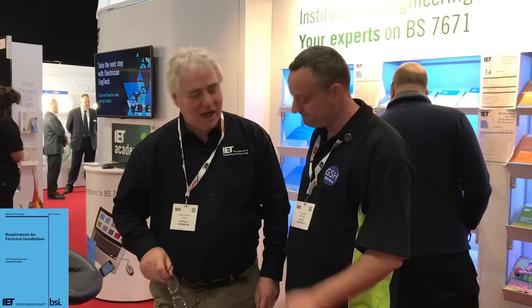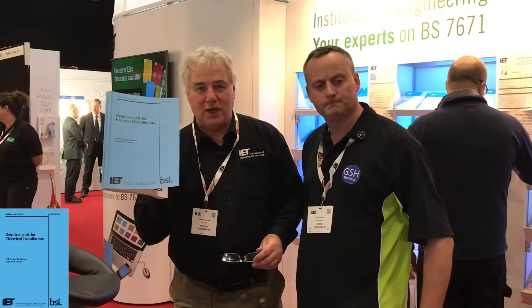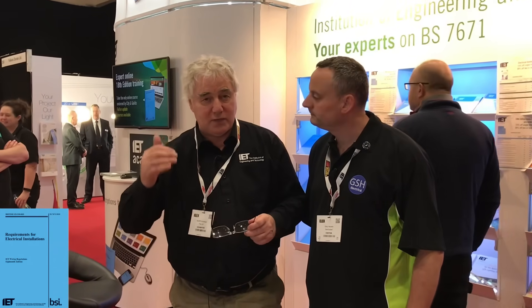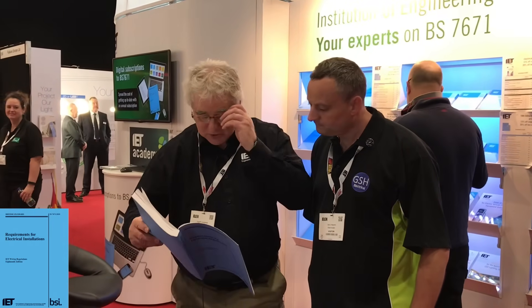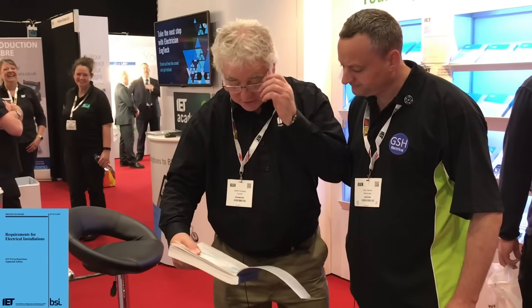I'm with Jeff, Chief Electrical Engineer at the IET, and he's going to give us a quick overview of some of the changes in the 18th edition. Hi — I'm Secretary of the National Wiring Regulations Committee, which is the committee responsible for the 18th edition. There are some quite key changes, things like section 722 on electric vehicles, which no longer allows PME as a means of earthing for electric vehicles unless you meet all the requirements of the wiring regulations — there are three key areas that you'd have to meet.